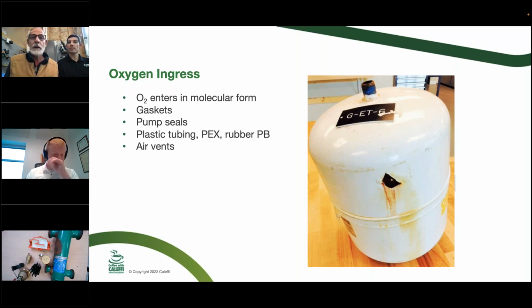the system. So in a perfect world, what we would have in our system is what's called dead water. And dead water is water that all the oxygen has been pulled out of. It's really hard to maintain that in the system. Oxygen molecules can get in through non-barrier tubing, through rubber tubing, which is an example of that. They can get in around packings on three-piece pumps, packings on valves, or pump seals, stuff like that. So it's really hard to keep a completely oxygen-free system.